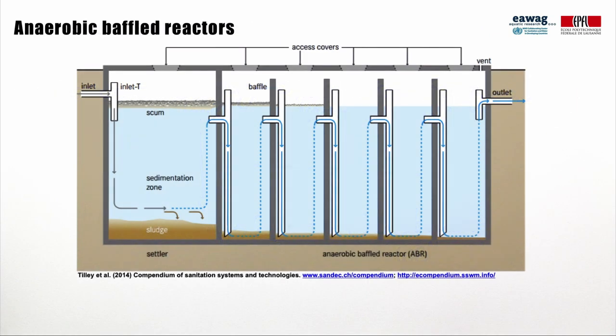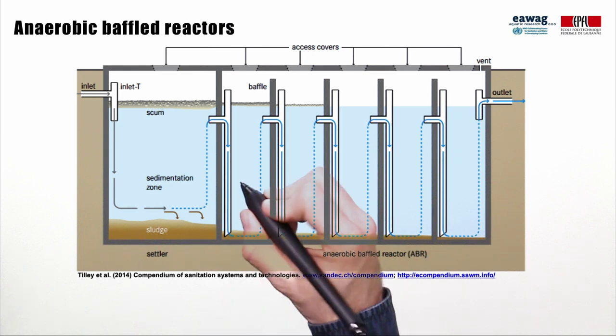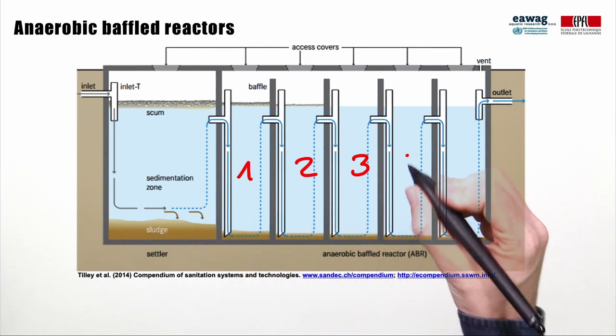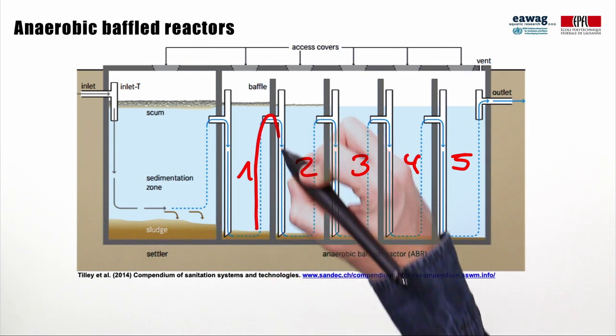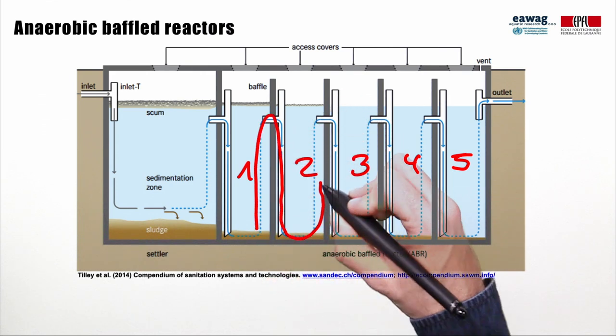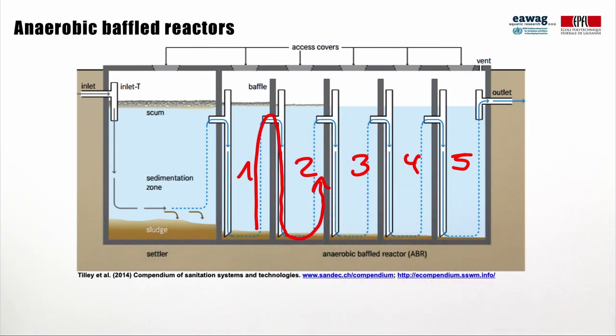This slide shows a schematic of an anaerobic baffled reactor as used in Devanali. These are concrete or plastic tanks with a series of baffles — in this schematic, there are five. They are designed for removal of organics. The baffles force the effluent to flow down into the next chamber and then up through a sludge layer. This contact increases the performance of organic removal, for example, in comparison to a septic tank.